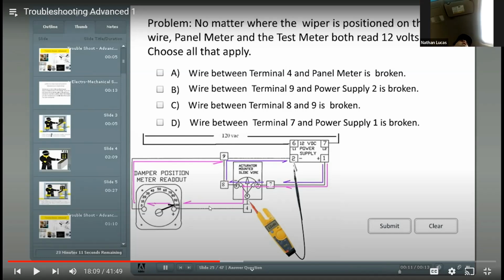Now, what we're trying to do in this is teach you guys how to break it down. Cut the thing up into manageable sizes to look at. We know in this case that we've got power between 1 and 7 because the meter's telling us we've got power that far. We know that power is also going through this damper position meter, the full 12 volts, because it's reading 100%. So that means wire 2 to 9 is okay. That leaves us with 9 to 2 being broken? Nope, that's not it. Wire between terminal 4 and the panel meter is broken? Nope, that's working because it's got full voltage there. So that only leaves the wire between terminal 8 and 9 is broken for an answer.